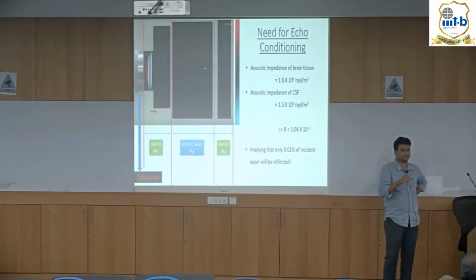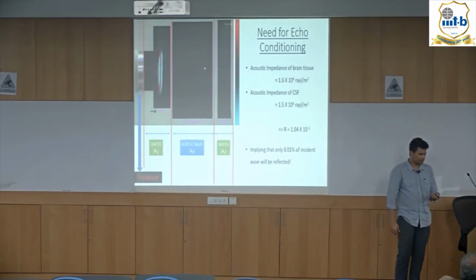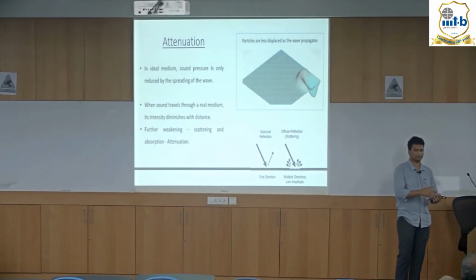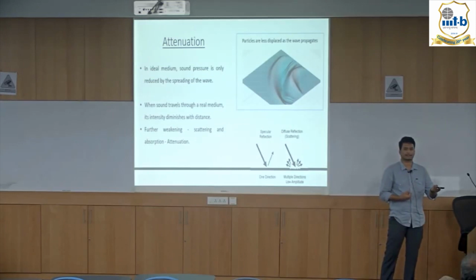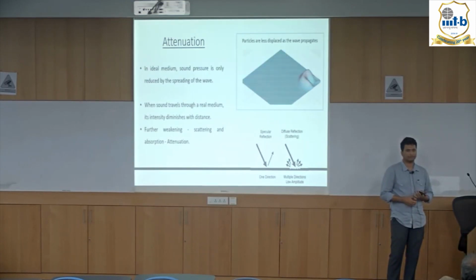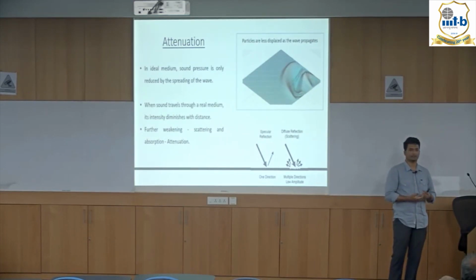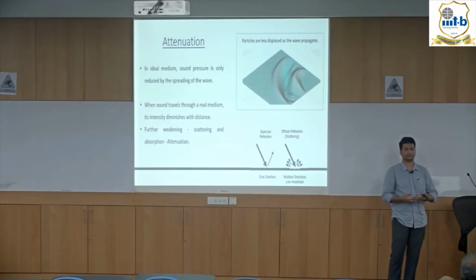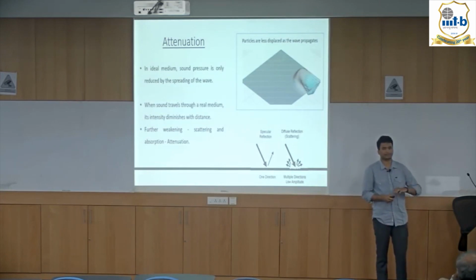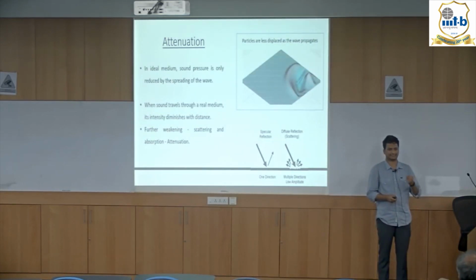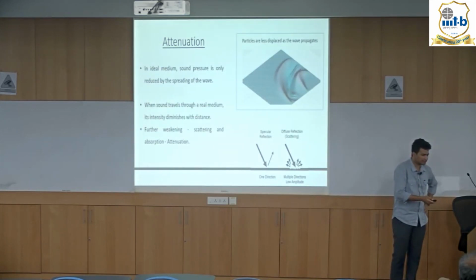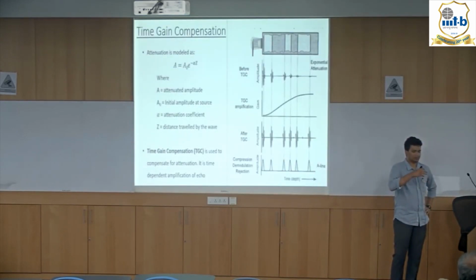So the echo strength is extremely low, and on top of that there is all kinds of attenuation as the echo passes through the medium of the brain before reaching the transducer for reception. There is scattering and there is absorption of the echo; it gets absorbed and converted into heat. So the strength of that 0.01% of the transmitted pulse reduces even further. So we need specialized circuits to capture these signals. That's the reason we need something called an AFE, which I'll be explaining.